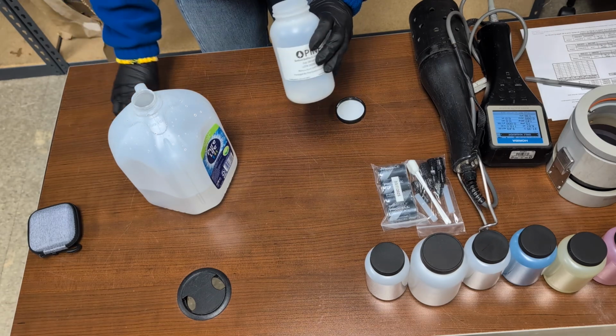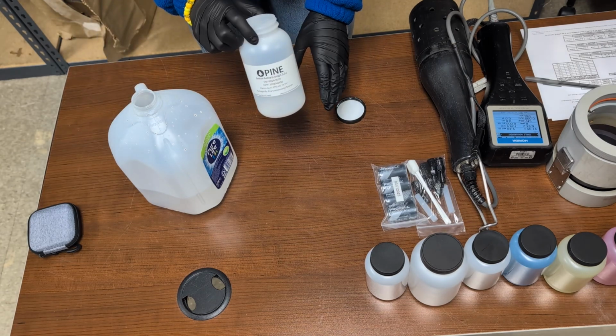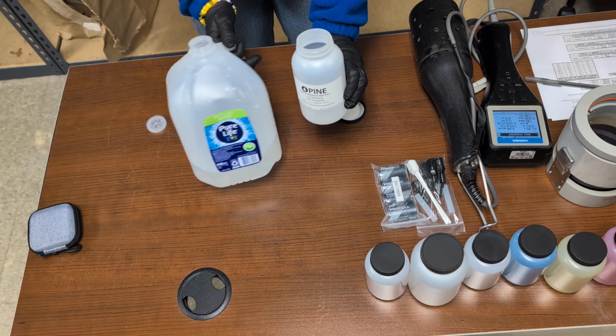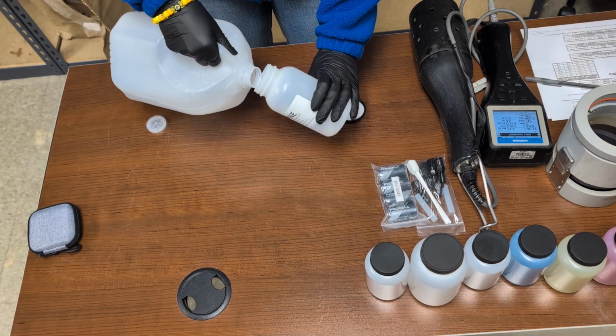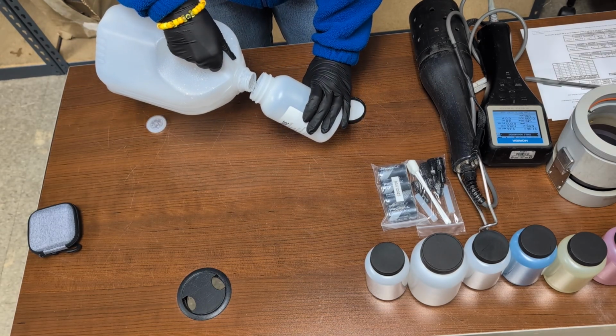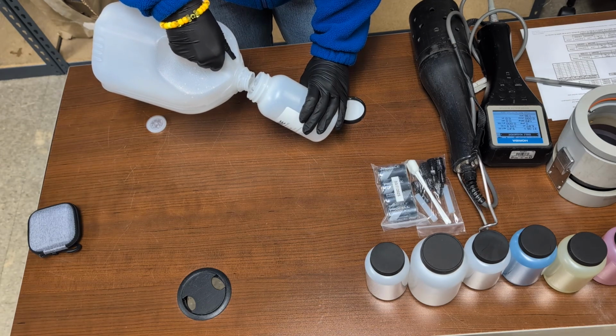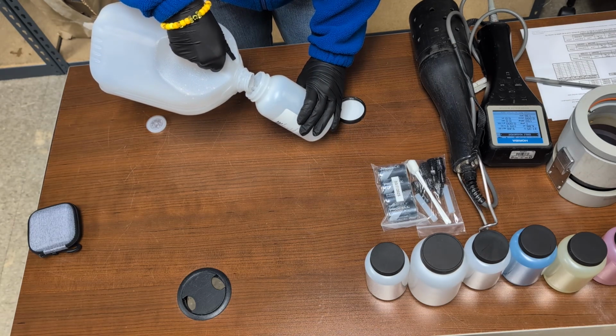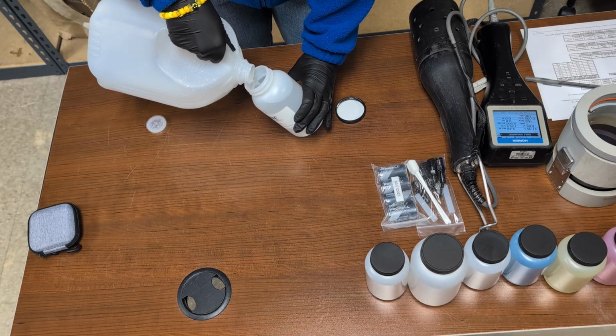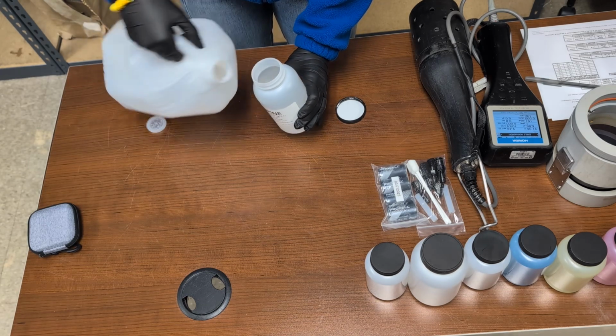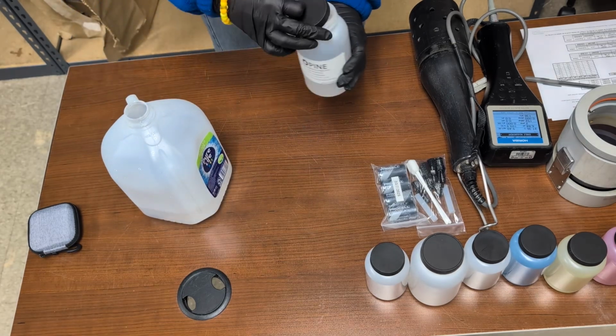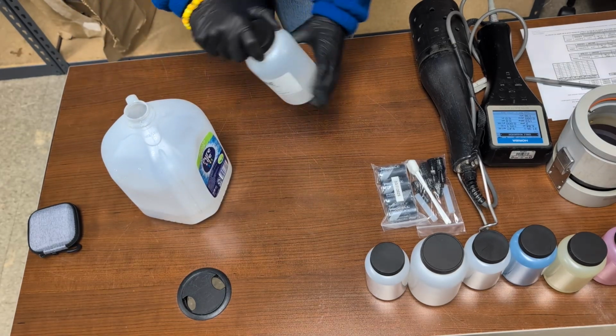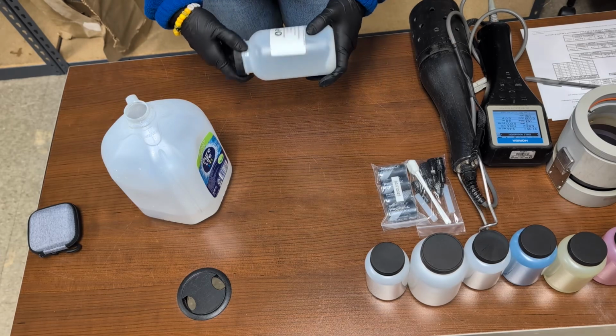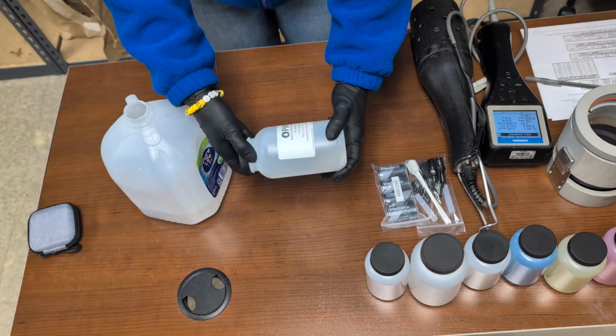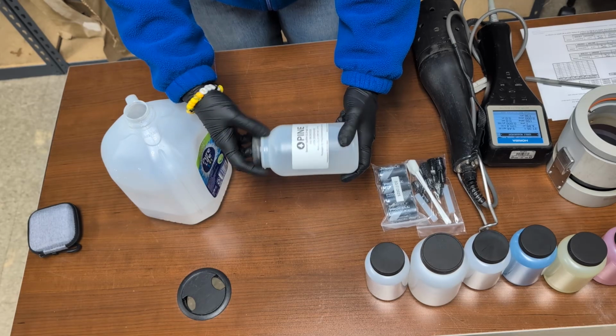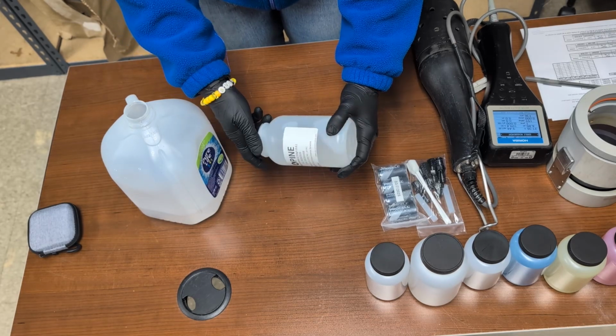So for the DO solution, you will be getting a bottle, and it'll basically have this powder down at the bottom. In order to create the DO solution, you're going to take DI water and pour it inside the cup, slowly, and you're going to tilt it so that no air bubbles get in, because remember we're calibrating for 0% DO, so we don't want to agitate anything or introduce any air bubbles into the solution. After you pour the water in, you're going to close the lid and gently swivel the bottle back and forth and rotate it until all the solution dissolves.